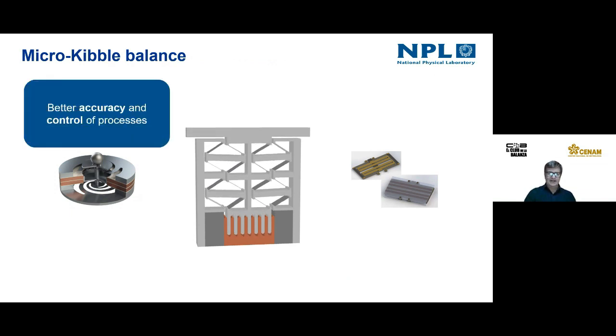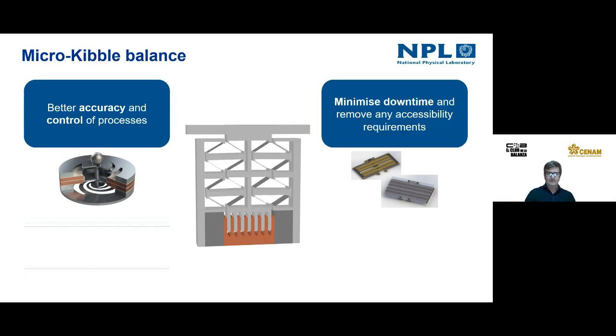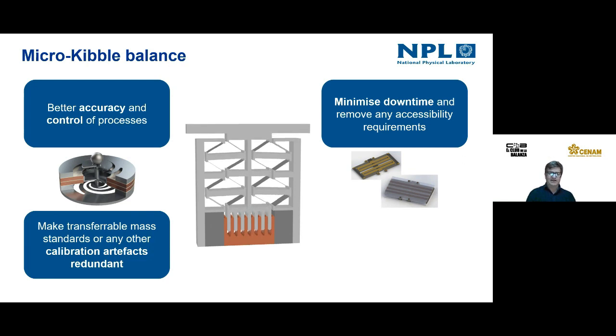So what do micro kibble balances look like? Most of them are conceptual at the moment, but it's essentially scaling the kibble technology down to a micro level where we can produce it on a MEMS device, a micro mechanical device, where it can hopefully be produced very cheaply and embedded in manufacturing processes, and also used to measure very small masses and forces. So it has the potential to improve the accuracy of process control, minimize downtime, and make transferable mass standards or other calibration artifacts redundant, since those small mass standards are inherently unstable and easy to lose.